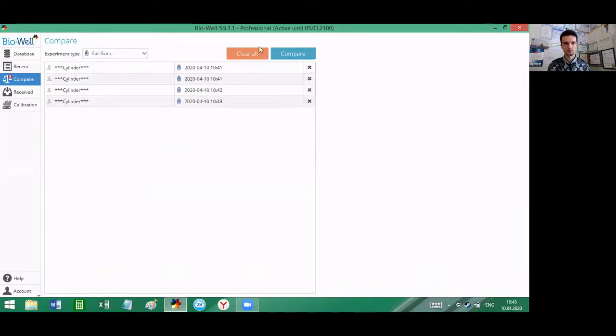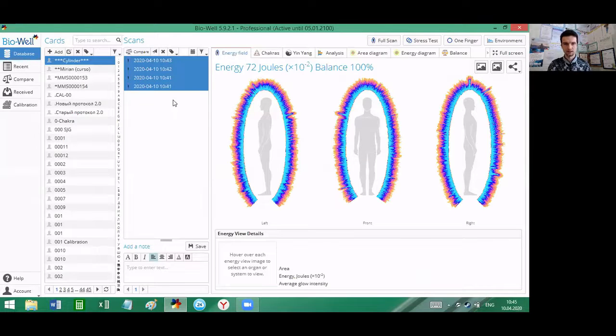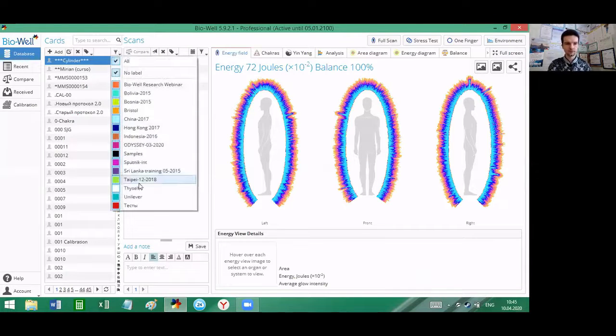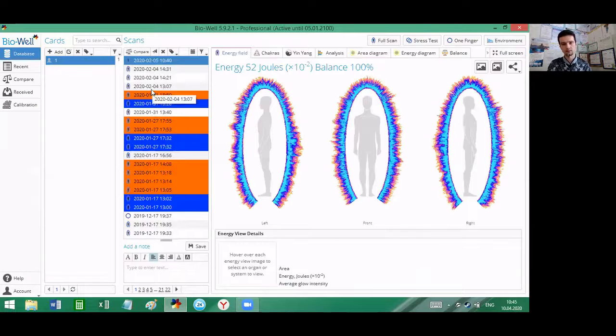So if we go back and we try to capture the person instead of the cylinder, then you will find out that the variability of the results of a person depends on the person, because the device itself, as we have seen right now, works with 99.3% stability. If you have variability of 5% or 10% or even 20%, it's all because of the internal properties of the person whom you are scanning. So the more stressed the person is and the less energy this person possesses, the higher the variability will be.